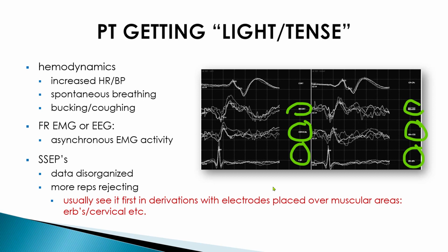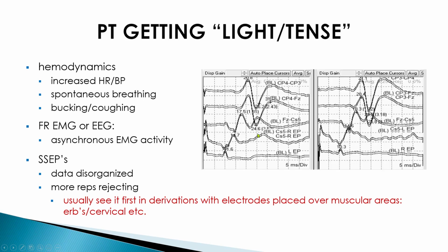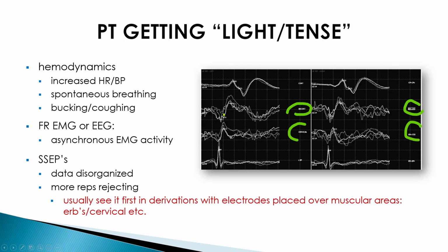So what happens when a patient starts waking up or getting light? They start getting tense. And this is just simply muscle activity that's interfering with our recordings.